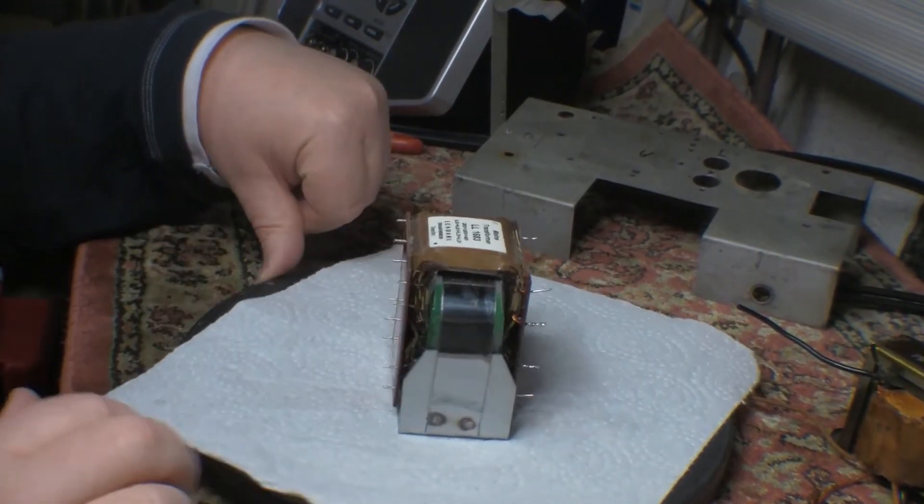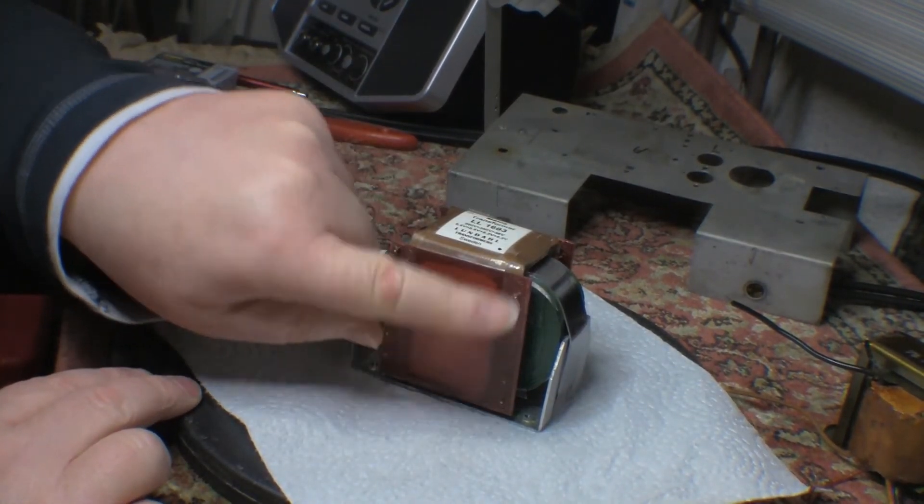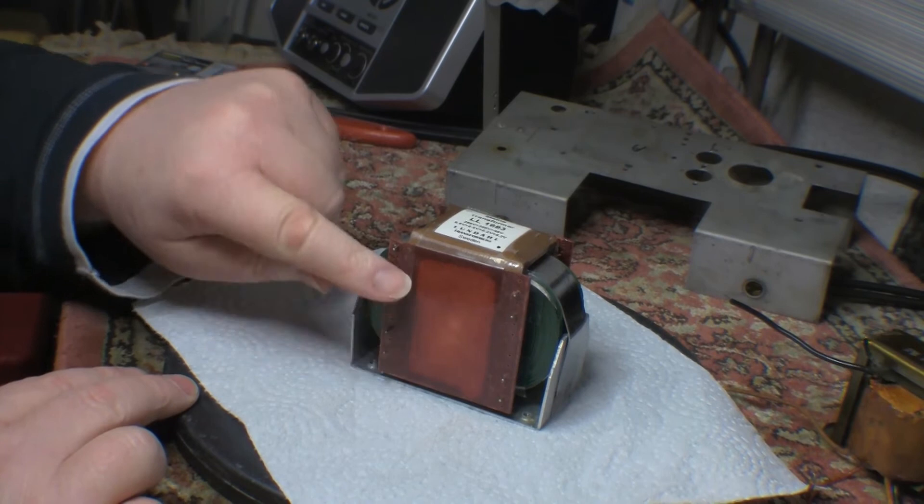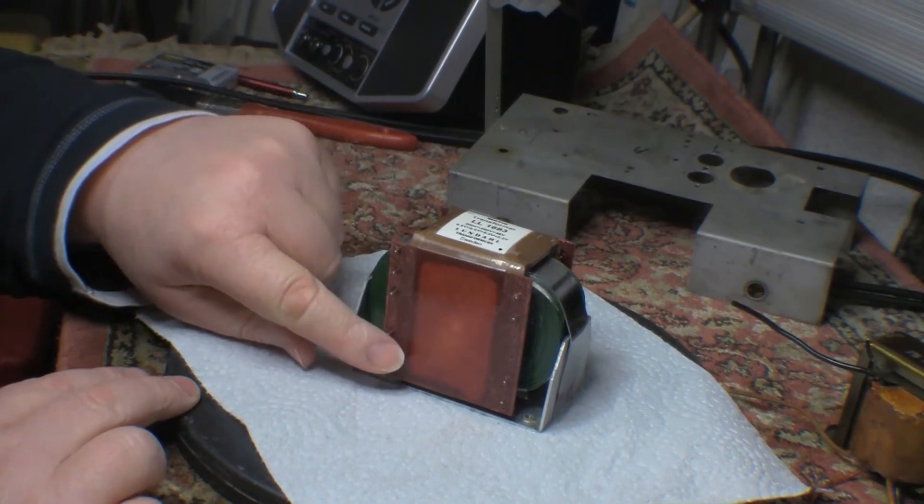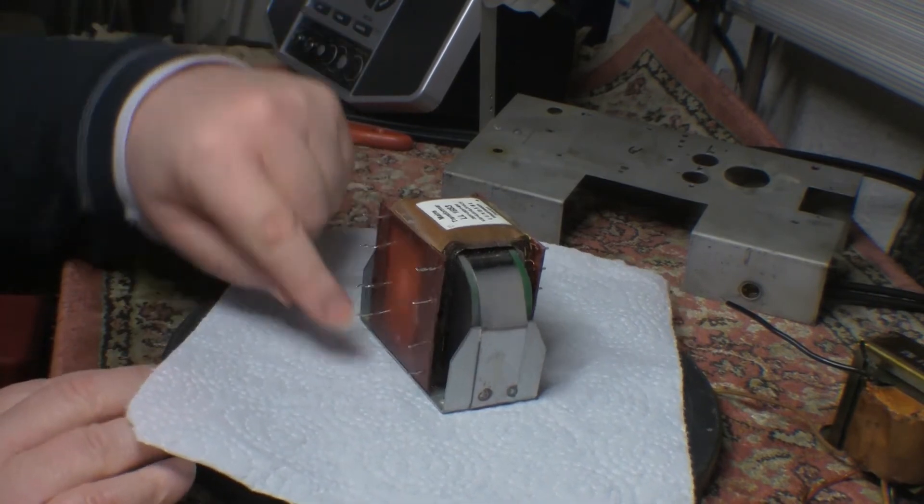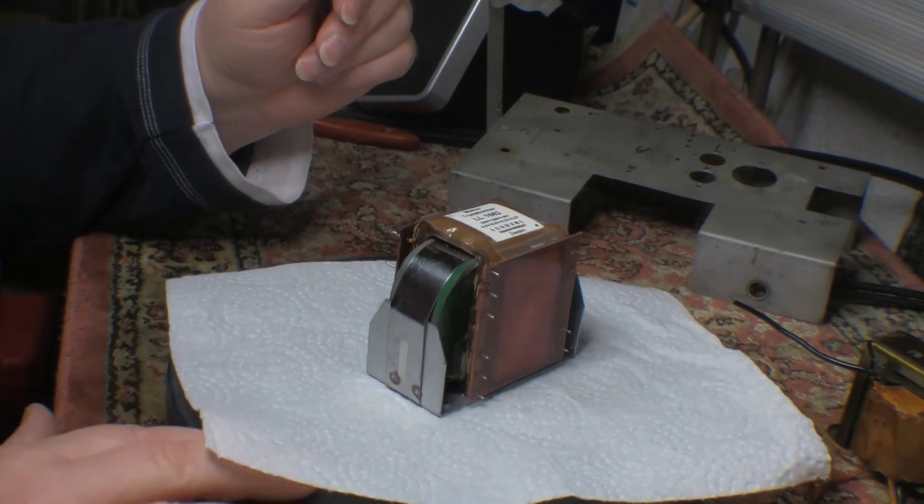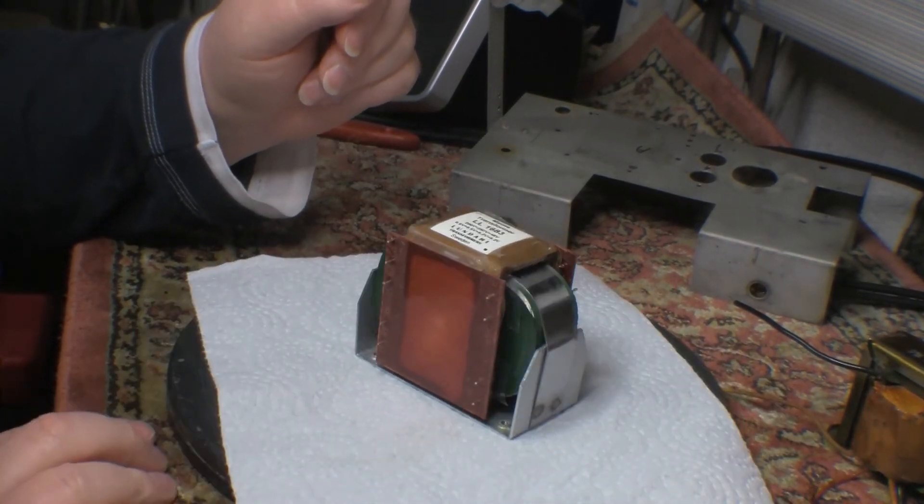Nothing much in the way of indications on it, but essentially these are the two primaries over here, these are the different secondaries in terms of high voltage, and then on the other side here we have different voltages for the 5.2 and 6.6 volt secondaries for filaments and stuff.